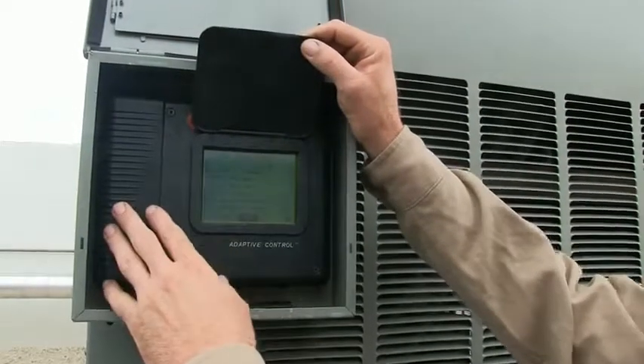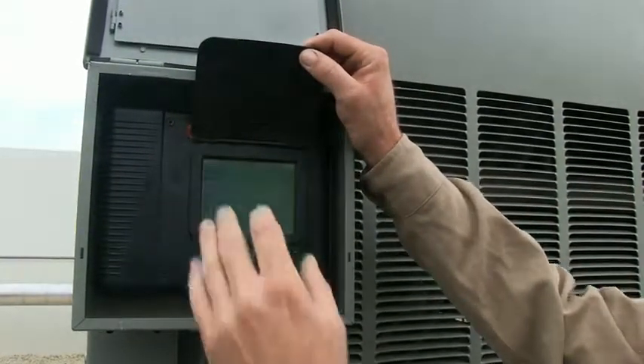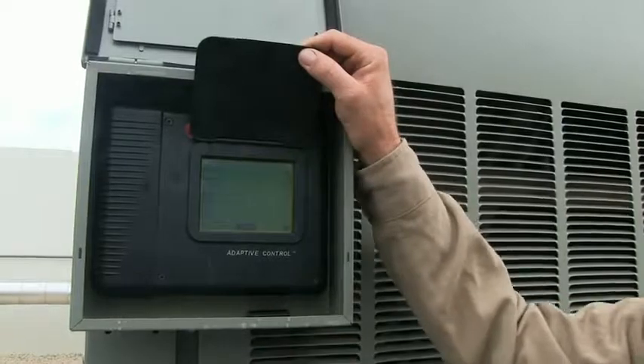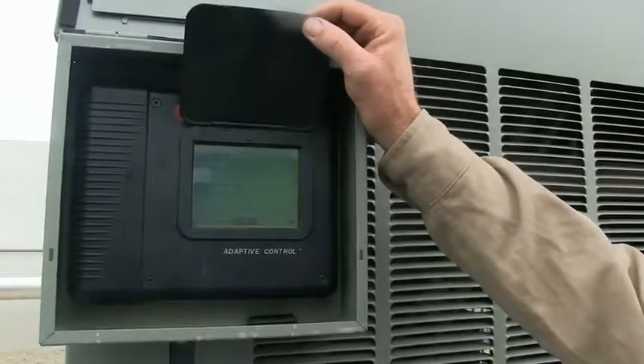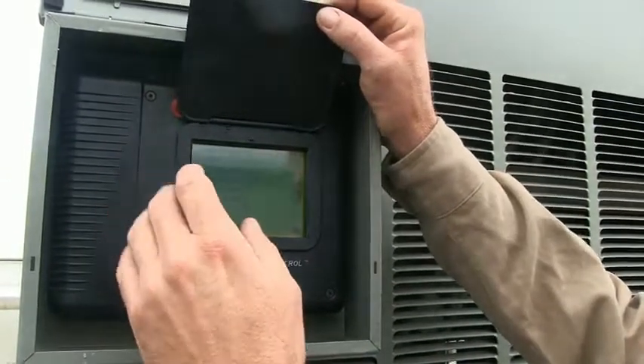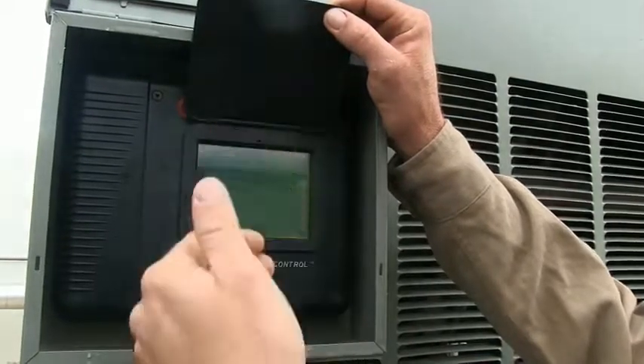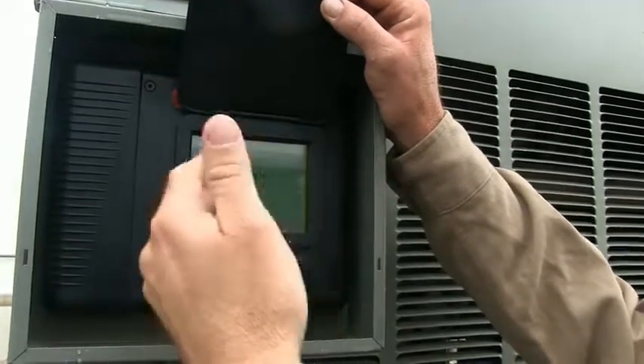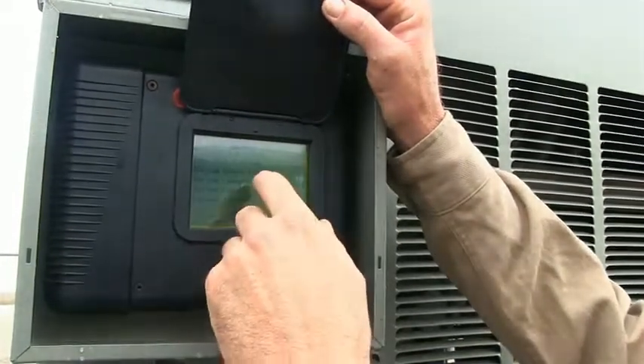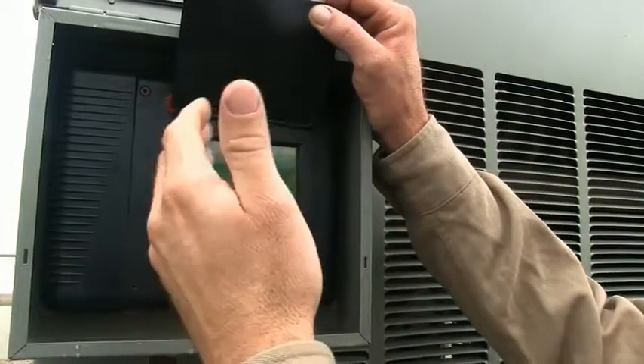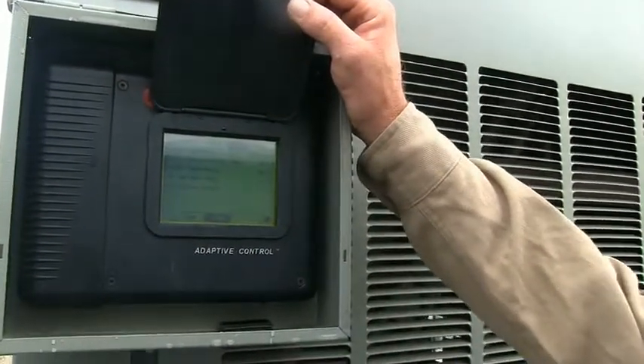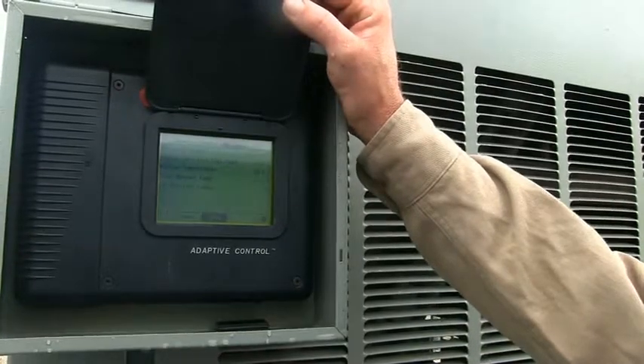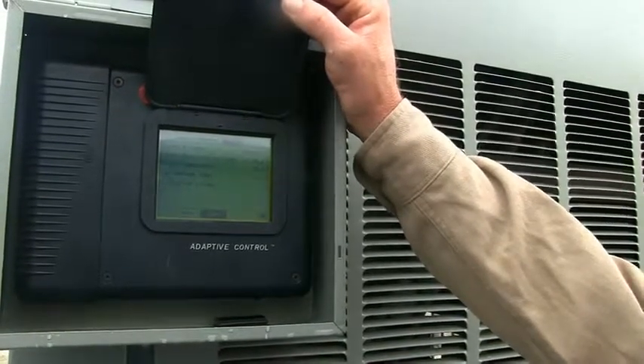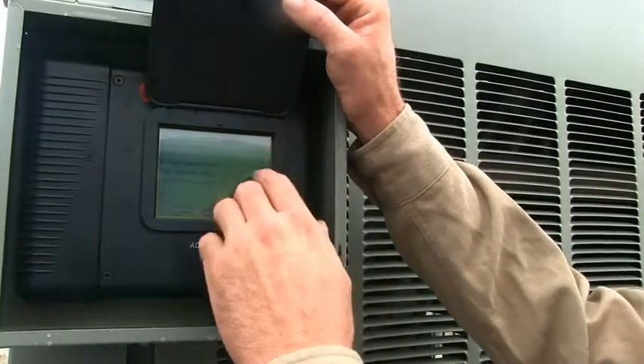The next category will be the reports. So you hit the reports button. Up at the top, it'll say evaporator. If you hit that button, evaporator, it'll show you the pump operation, the temperatures, the VFD commands, and so on. If you hit circuit 1, it'll show you refrigerant pressures, refrigerant temperatures, suction line temp, approach. Same thing for circuit 2.